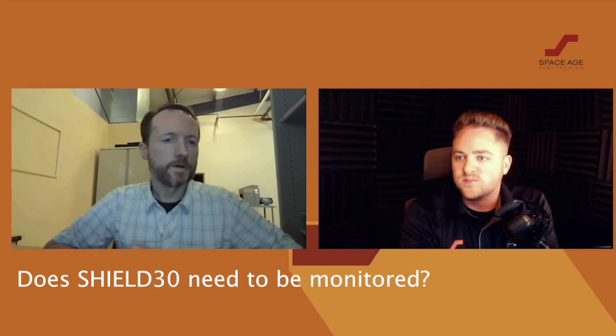Oh, okay, that makes sense. What about monitoring? I heard that they're wanting these systems to be monitored by the building fire alarm panel. Is that true? Yeah, so these systems are monitored like any ancillary life safety systems. These systems are required to have contacts so they can be monitored, alarm, trouble, and supervisory from the fire alarm panel. So yes, we have a set of contacts for any troubles. The reason for that is if anything goes wrong with the system, it can signal for trouble over the dialer for the fire alarm, the communicator per se. Oh, okay, that makes sense now.